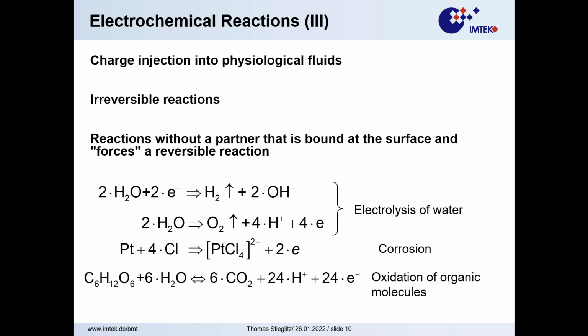So you might have an electrode, but there's no contact any longer, or you have lost your whole surface area or something like that. That's one of the disadvantages of platinum, that it's really hiding a little bit its corrosion with that mechanism. And if you would do it even worse, then you could oxidize organic molecules. And this is nothing we want to do with electrical stimulation, that we jump into whatever metabolic circuit and oxidize whatever is around.